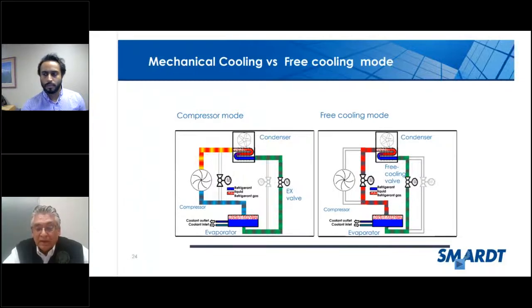I guess I've done both. Yeah, and if you look, there's also an opportunity to use free cooling inherent to the machine, where there's another set of valves where you use the natural heat transfer capabilities of the evaporator and the condenser, like a free cooling mode. Using a plate heat exchanger in a cooling tower, you can get about 30 or 40% of the total capacity. If it's a 100-ton machine, you may be able to get 40 or 50 tons of free cooling. Same happens for a free cooling mode. We're using a refrigerant cycle within the chiller itself. No additional heat exchangers are required.